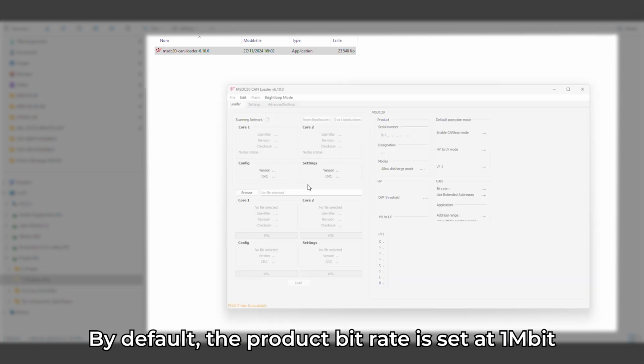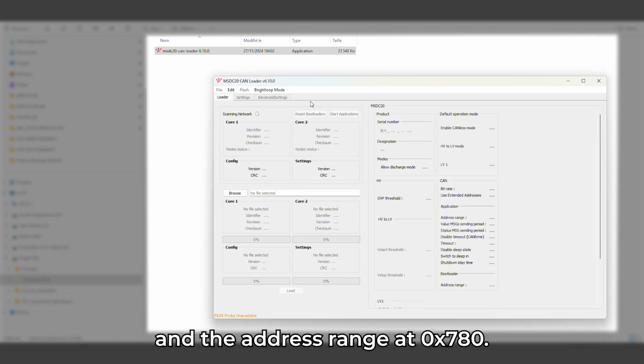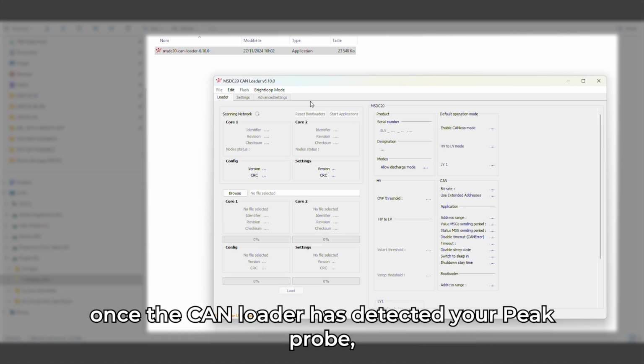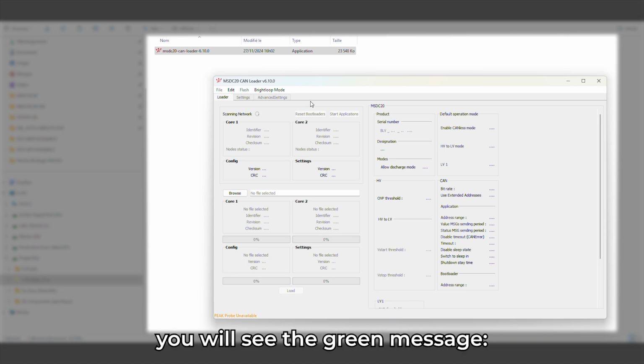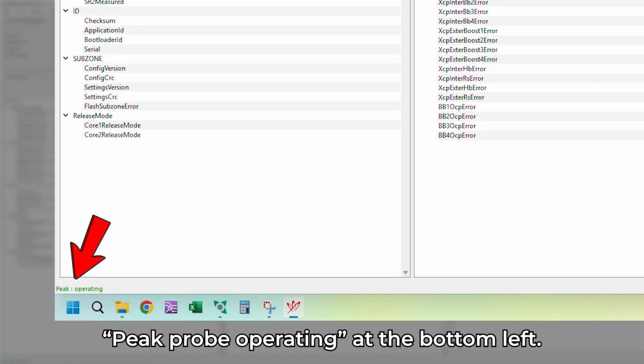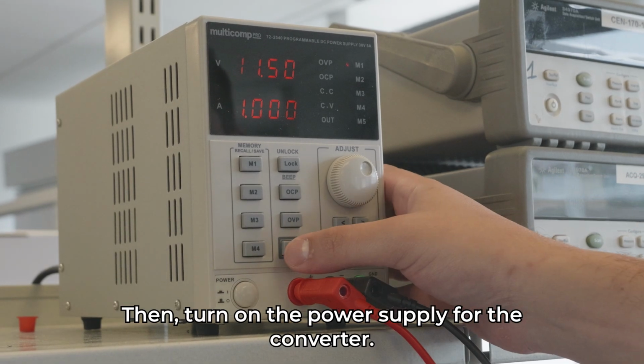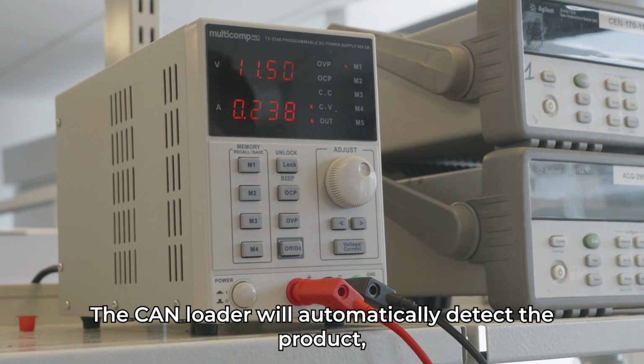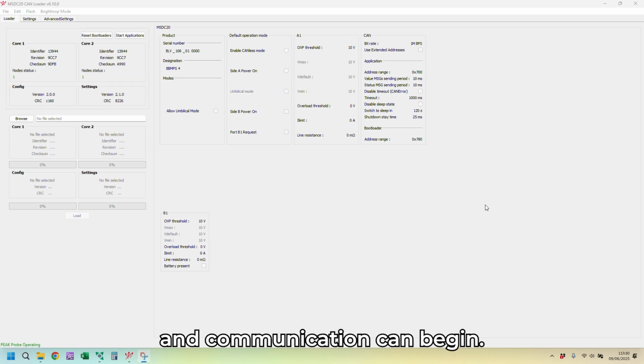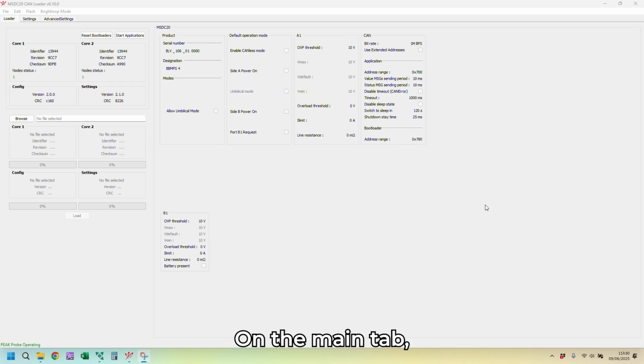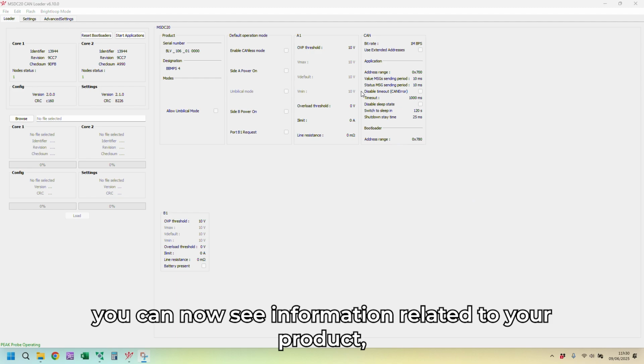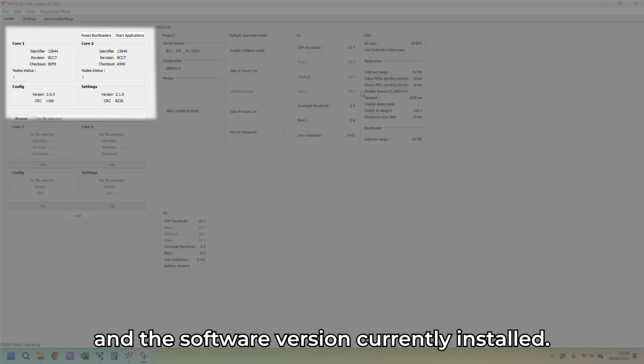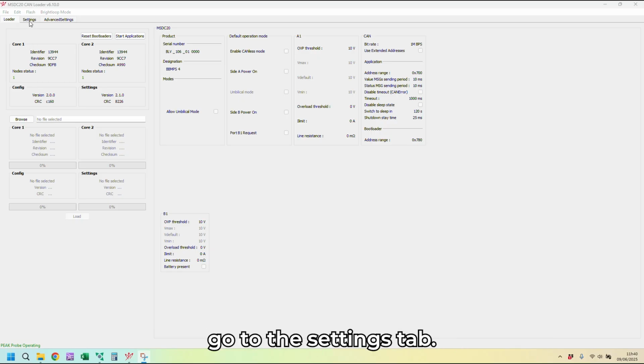By default, the product bit rate is set at 1 megabit, and the address range at 0x780. On the Loader tab, once the CAN loader has detected your peak probe, you will see the green message, Peak Probe operating at the bottom left. Then turn on the power supply for the converter. The CAN loader will automatically detect the product and communication can begin. On the main tab, you can now see information related to your product, including its configuration and the software version currently installed. To configure your product, go to the Settings tab.